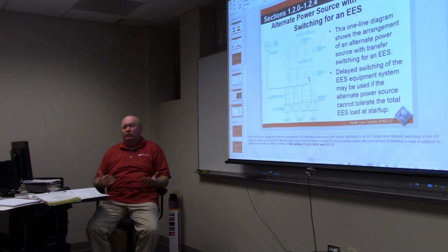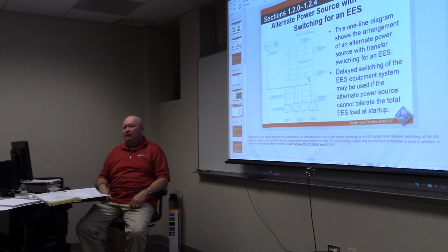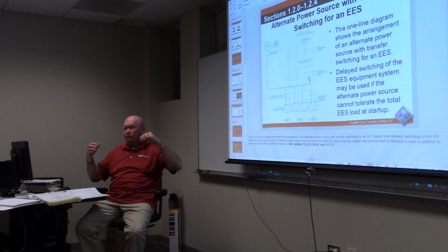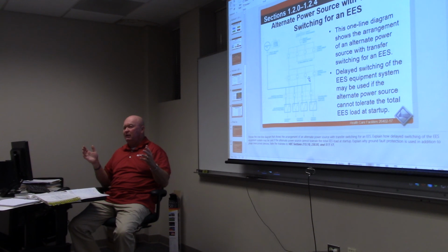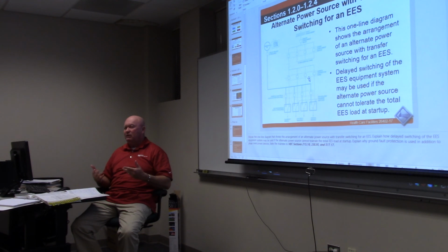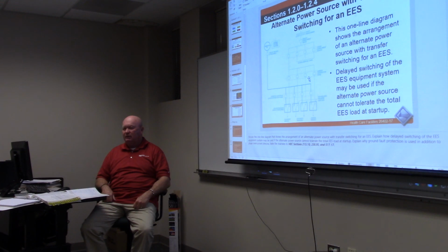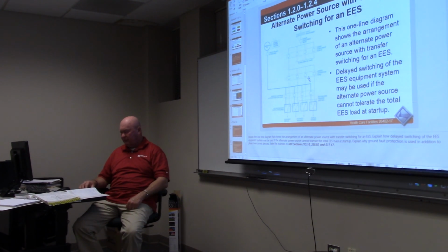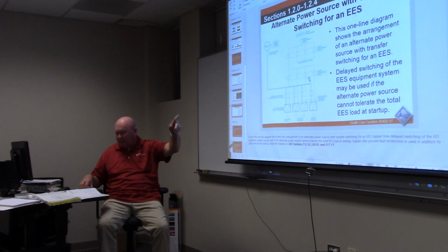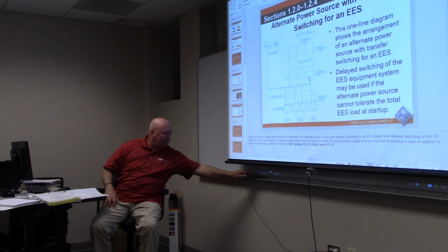That's because that's where your largest load is. On a building we did, we had 2 large rooftop units, and the generator wasn't sized to run the whole building, but they wanted the rooftop units on. Once they're up and running, the generator will handle the load, but the surge if both tried to come on at the same time would be so much it would kick the circuit breaker on the generator—so you avoid that with delayed switching. Does everybody understand this single line diagram and what we're doing there?